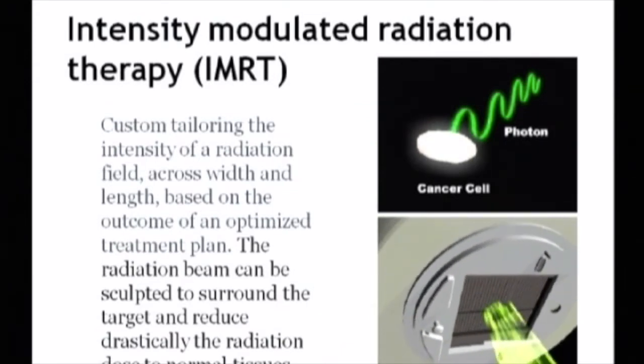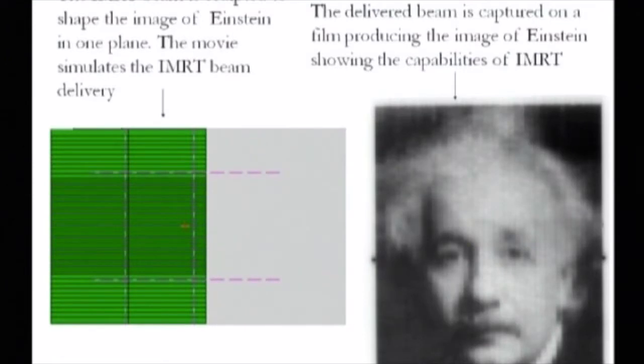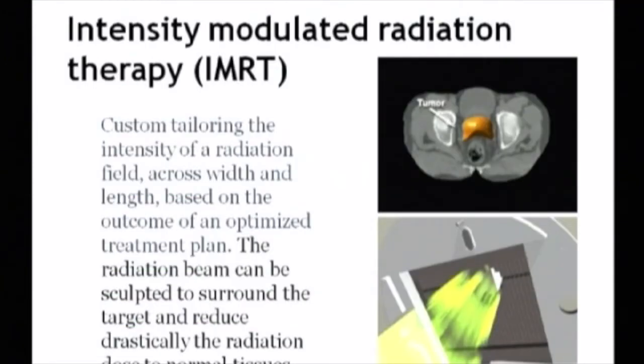Here, the LINAC machine really just generates a flood of X-rays, and we have collimators on the LINAC machine that actually move across. So it's really intensity modulated radiation therapy, which means that we modulate the intensity delivered by modulating the time of exposure to tissues. So you have a collection of really tiny lead fingers that go from one side to the other side. So the slower it moves, the more exposure you have to the radiation beam, the faster it moves, the less radiation one would get.